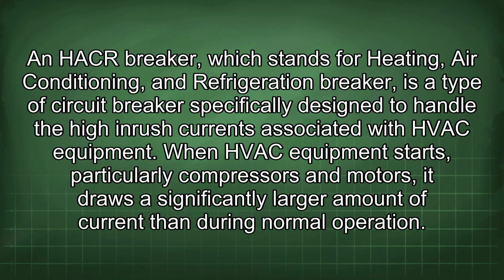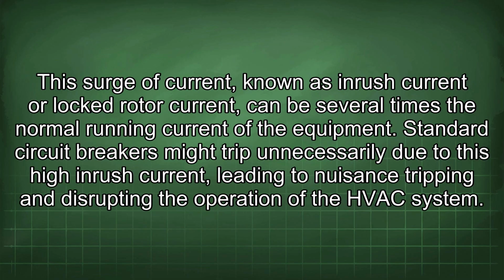An HACR breaker, which stands for heating, air conditioning, and refrigeration breaker, is a type of circuit breaker specifically designed to handle the high inrush currents associated with HVAC equipment. When HVAC equipment starts, particularly compressors and motors, it draws a significantly larger amount of current than during normal operation. This surge of current, known as inrush current or locked rotor current, can be several times the normal running current of the equipment. Standard circuit breakers might trip unnecessarily due to this high inrush current, leading to nuisance tripping and disrupting the operation of the HVAC system.